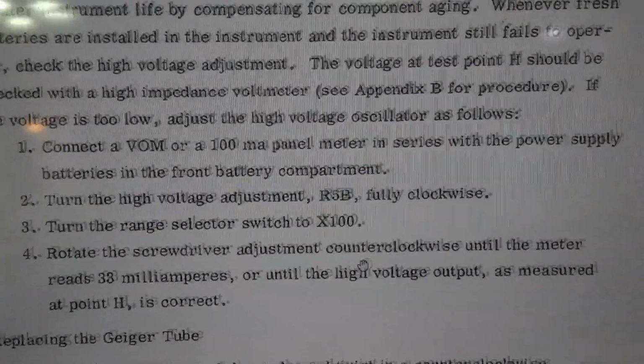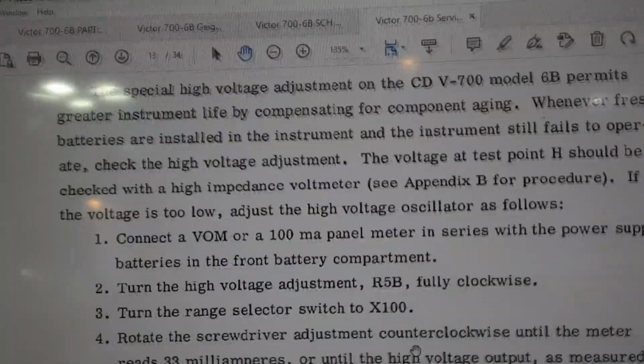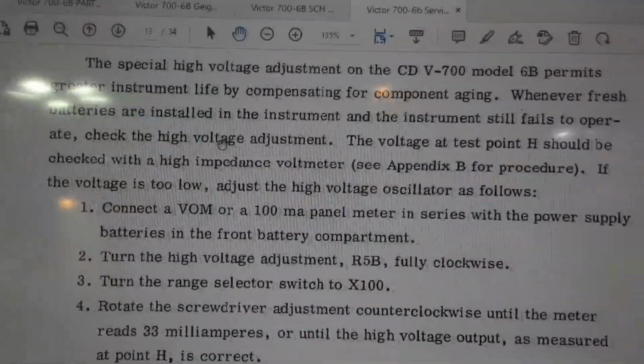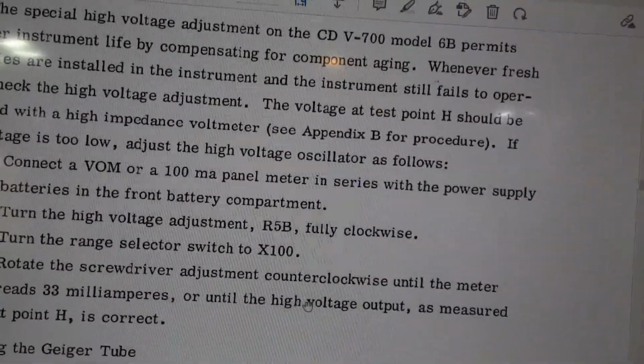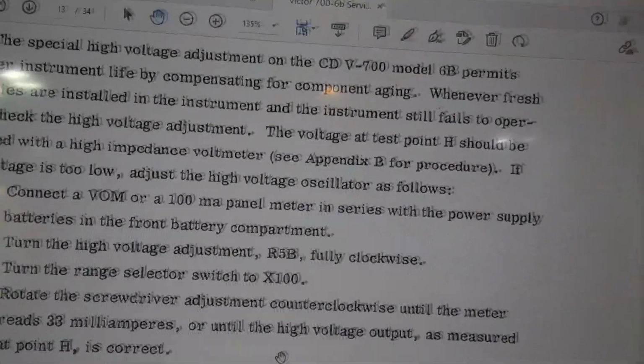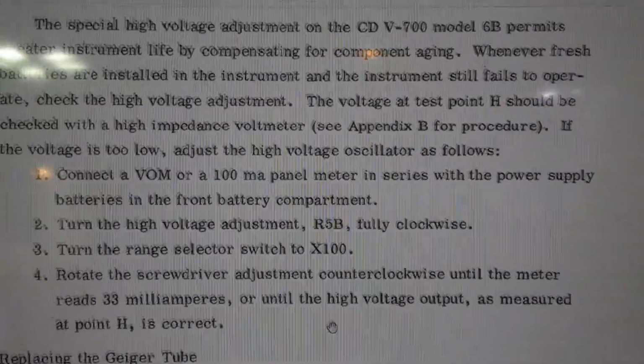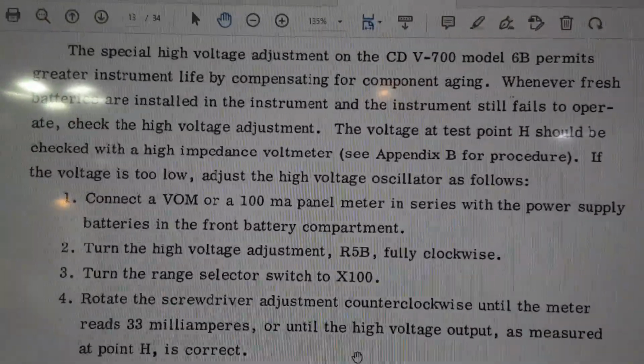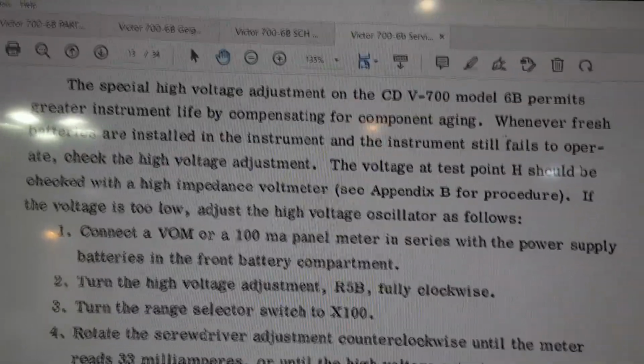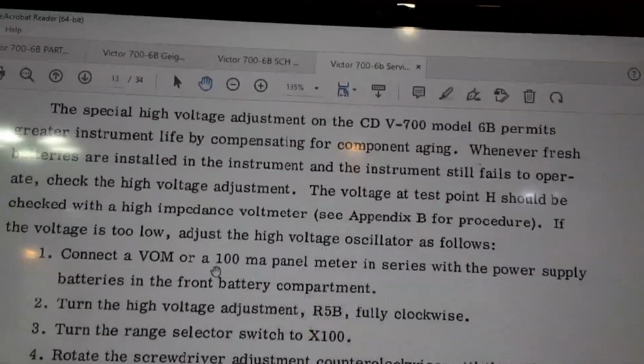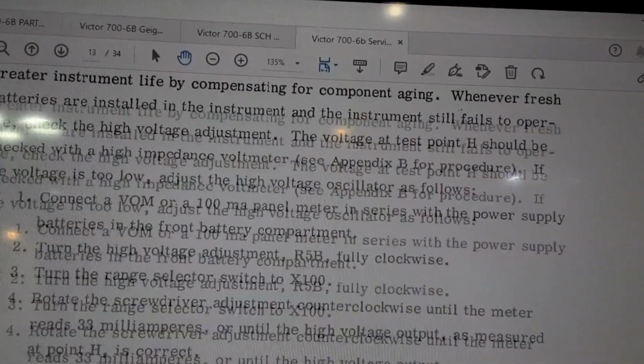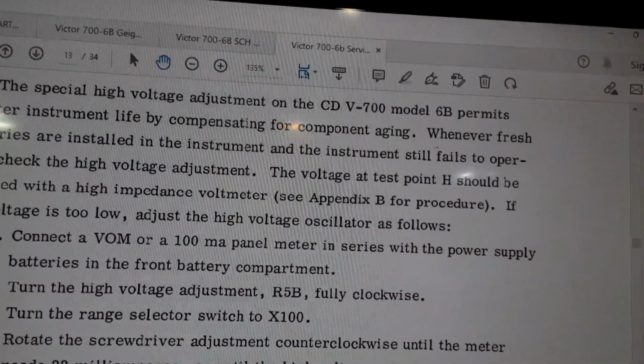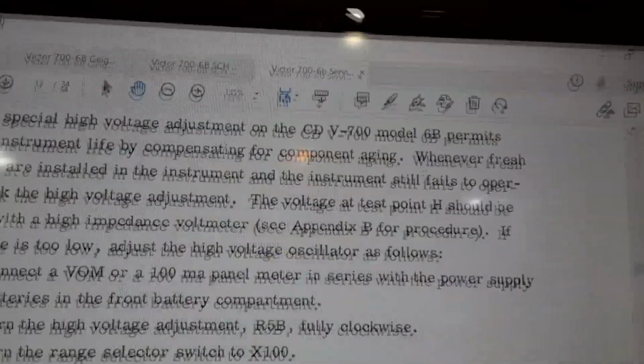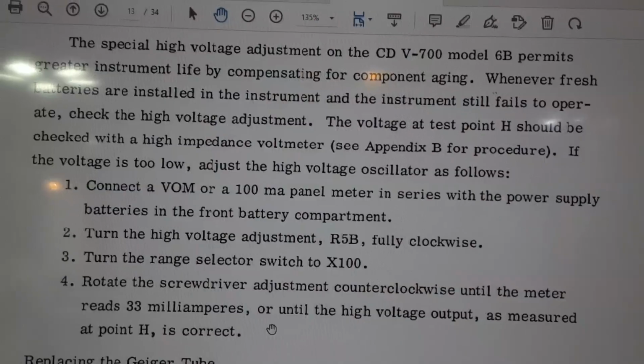Okay, I was able to find a better document on servicing this, and of course it gives you a little bit more information, but basically it said the same thing that I was saying, that you really don't need to actually measure the high voltage. You can if you have a high voltage probe. I don't have one. I don't work on TV sets, tube television sets and things from that era, so I don't deal with really high voltage. It's only 900 volts. Unfortunately, most of my meters do not go up to 900, and it's 900 plus or minus 20%, so it can actually be well over 1,000 volts, and I don't have a meter that goes that high.